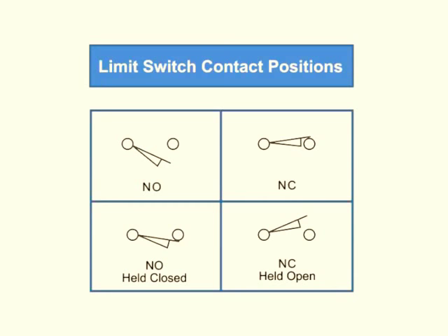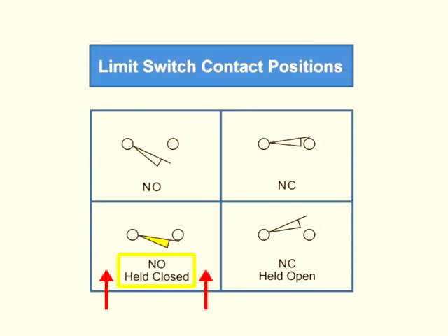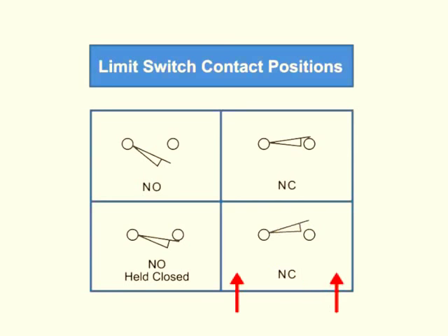In this schematic diagram, the direction from which a force must contact the switch's actuator is indicated by the triangle below or above the switch. A normally open limit switch will remain open until the actuator is acted upon by an outside force or object, thus holding it closed. A normally closed limit switch will remain closed until an outside force or object holds it open.